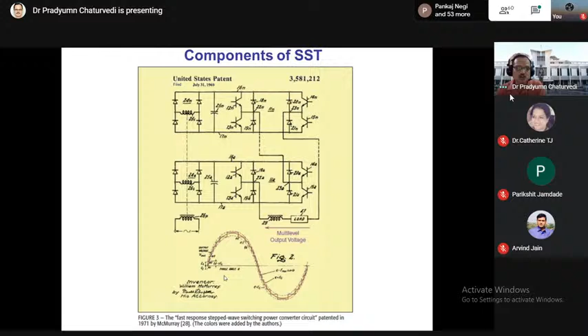So this is the phase stack, converter cell, DC-DC converter, and protection at LV and MV side, and everything is inside this. Now we can have one flexibility: every output of this can be given to separate AC also. Otherwise, just connect this in input series output parallel, or input parallel output series type of connections, depending upon voltage current requirement of the load side and available rating at source side. So this is the major advantage of this type of application, and it is not possible without using multi-level converters, because otherwise you have to go for very high power rating devices.